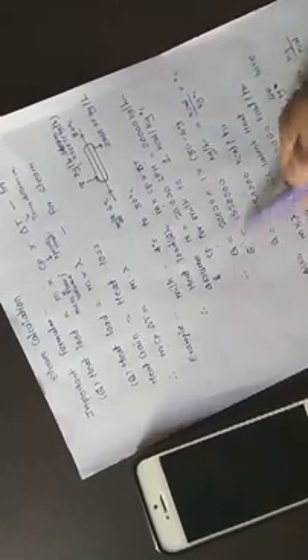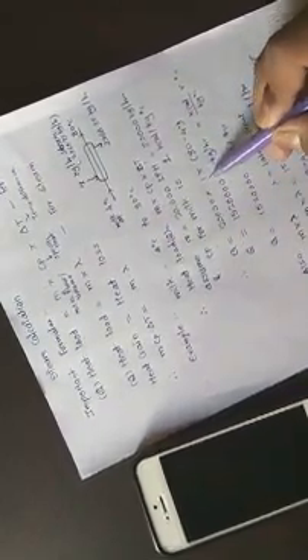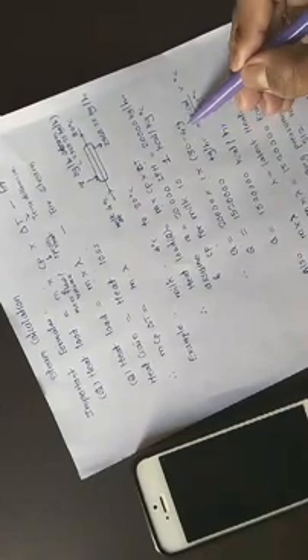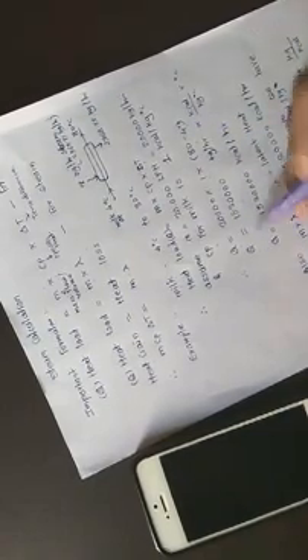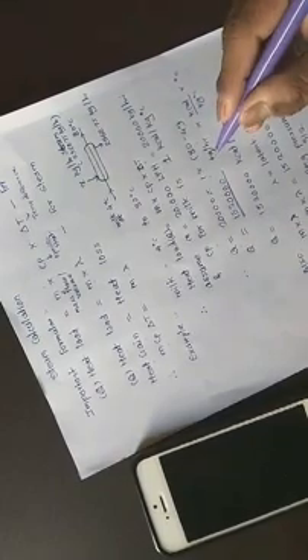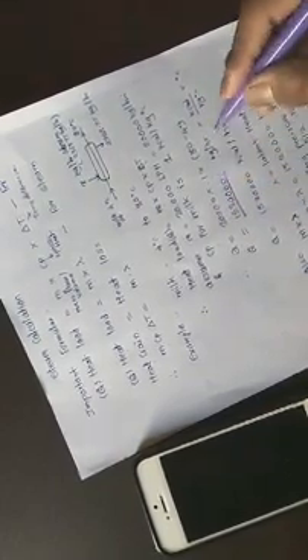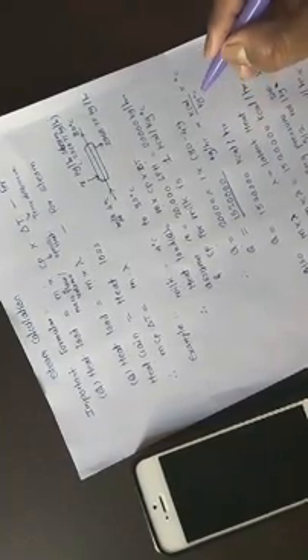Generally for milk and water, we assume 1 kilocalorie per kg degree Celsius. So we have M, then Cp and delta T. What is delta T? 80 minus 4. So Q is equal to 20,000 into 1 into 80 minus 4. When you calculate Q, you will get this figure. And also look at the units. What is kg per hour? This is the kg per hour milk flow rate.